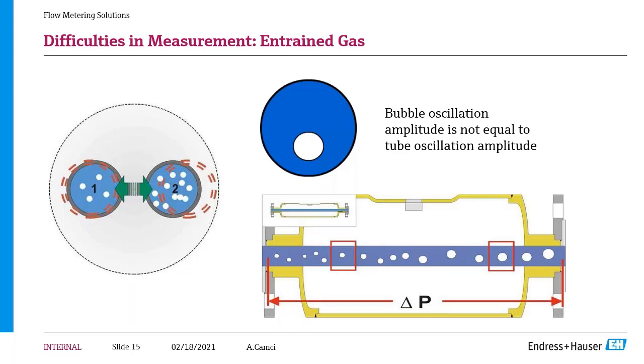The normatives and also the meter technology say the measurement should be in single phase. It should be either liquid or gas. When there is entrained air and trapped air inside the liquid, the oscillation frequency of the bubbles or the air molecules is different from the liquid molecules, and this will create an error in the measurement.